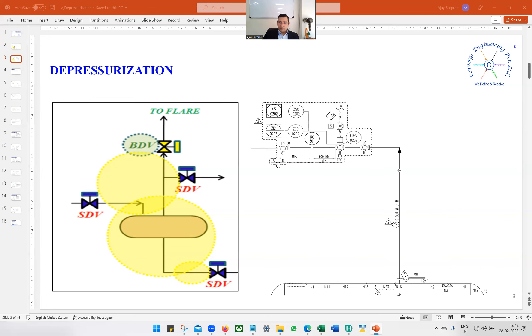On the P&ID the system would look something like this. We have an 8-inch line — it could be a different line size — which is the depressurization line. It goes to this EDPV, emergency depressuring valve, followed by the restriction orifice. Here the tag number is RO501, and then it will be sent to the flare header or to a safe location depending upon what the content is.